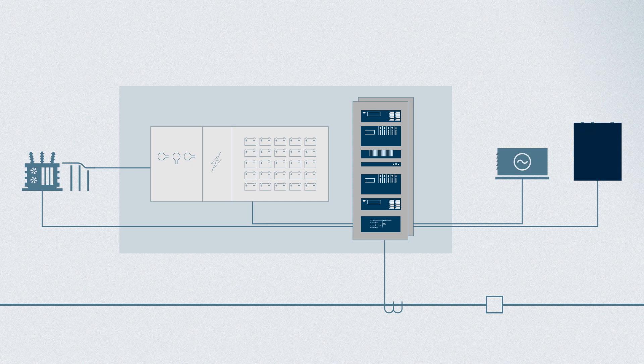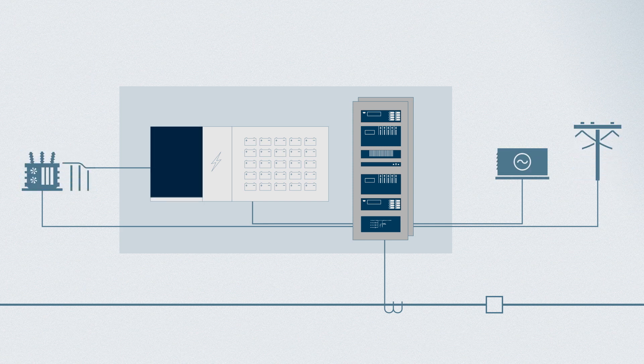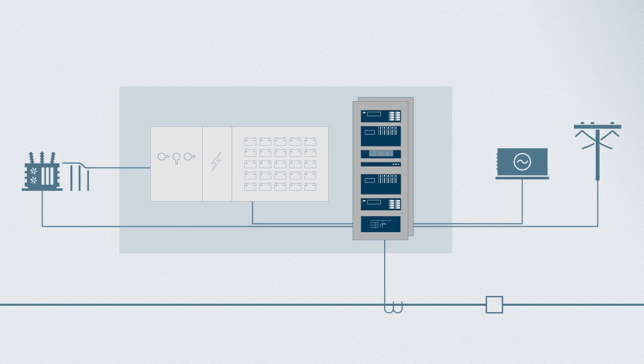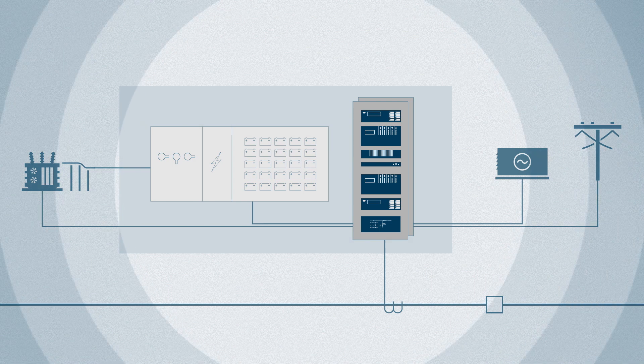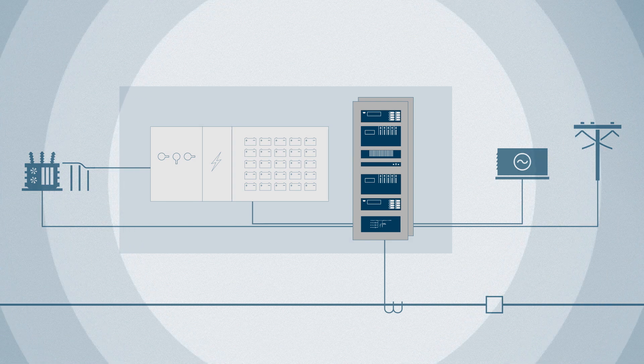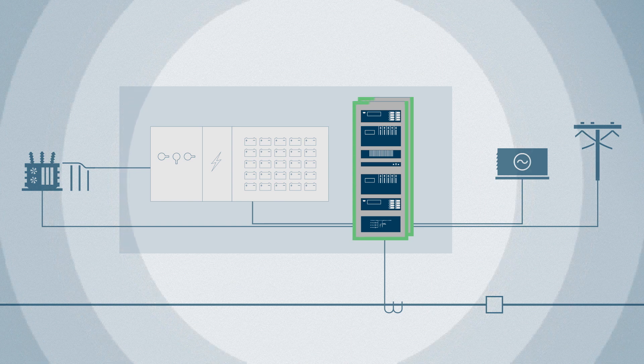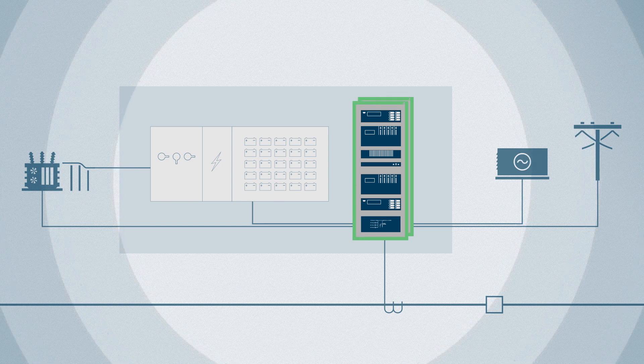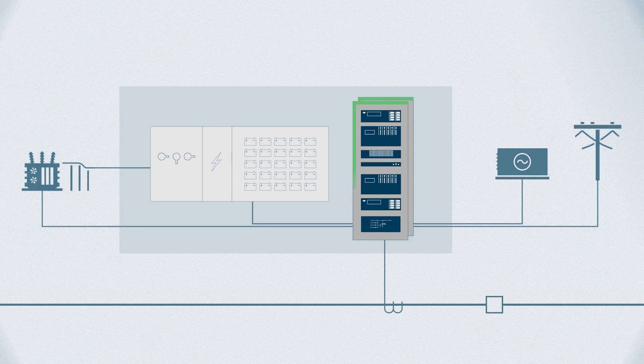This ensures continuous, uninterrupted service in the event of the loss of any individual source. Now, if a momentary interruption or voltage sag on the DC system occurs, the internal energy storage capacitors in the redundant power module allow protection and control equipment to ride through the event, keeping critical equipment safe.